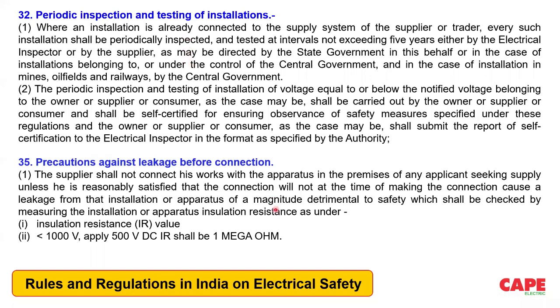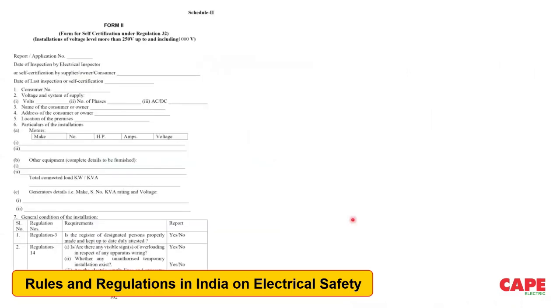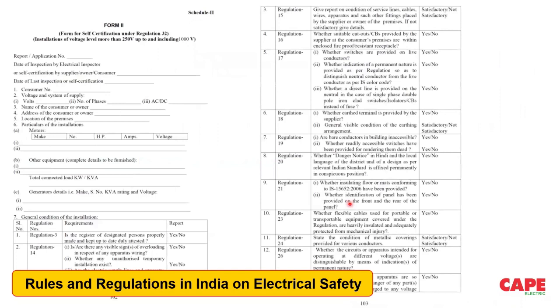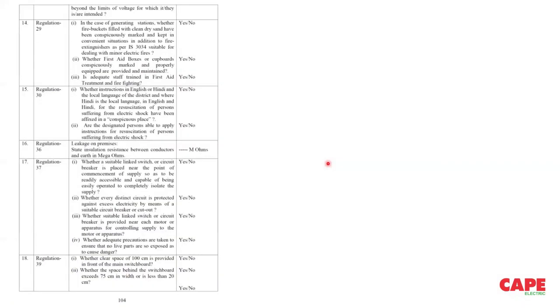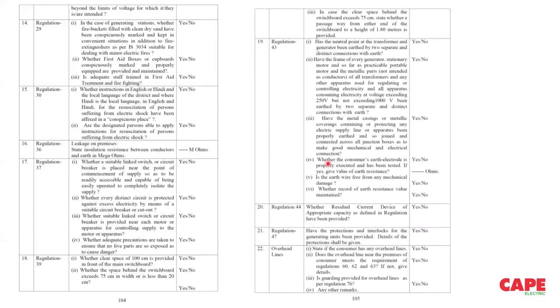Also, the regulation explains the formats. The reason for showing these formats is that probably in future, people will start doing the electrical safety audit as per this particular format. Please note that this format, which is Form 2 in the upcoming regulation, is actually talking about compliance to the regulation. For example, in a consumer premise, you see regulations 15, 16, 17, 18. This format is asking about compliance to the regulation. And in my view, if you do a compliance as per this particular format, of course, electrical safety on a large scale cannot be achieved. In a residential case, it's okay, but in a large building, it will be very difficult to achieve electrical safety. In an industrial or a large commercial installation, it is very difficult.